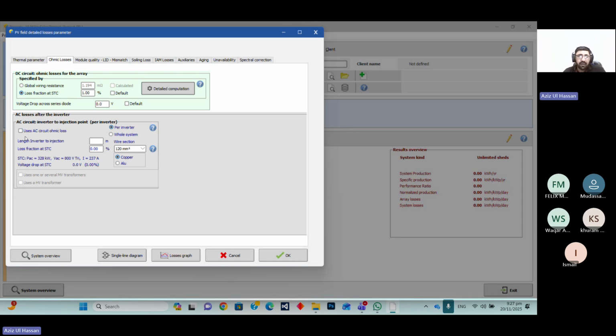Then we move on to the AC circuit, the AC losses after the inverter. Basically, in the central case, because the inverters are installed near our LV switchgear and the transformer, no cable will be installed, as it is a centralized containerized solution. The inverter will be installed in the same cabin where our inverter transformer is available. So here just 10 meters, or 6 or 7 meters, of busbar connection is available. But in the case of the string inverter, it is installed in the field and the transformer is installed at some other location, so we have to do the cabling in between, from the string inverter to the LV switchgear of the transformer.